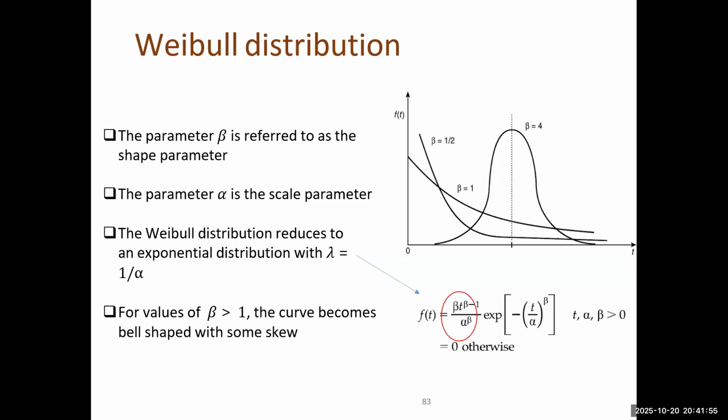And for the next several years, as we mentioned before, we now come to the what? The random failure. The fuses fail only rarely and unpredictably, perhaps due to a random power surge. And for the third stage, where beta is greater than 1, let's say after 10 years, the fuse's internal material begins to what? Begins to degrade due to sustained thermal cycling. So the failure rate now increases steadily with time. So that becomes our Weibull distribution for our real-world application.